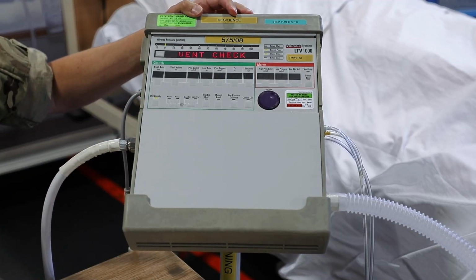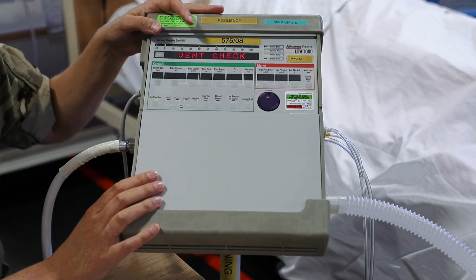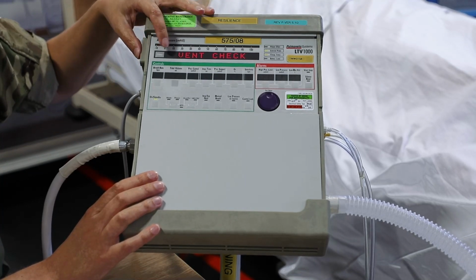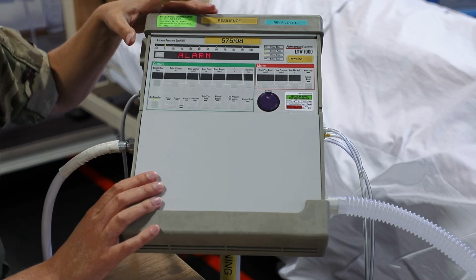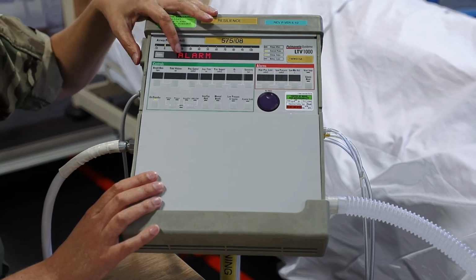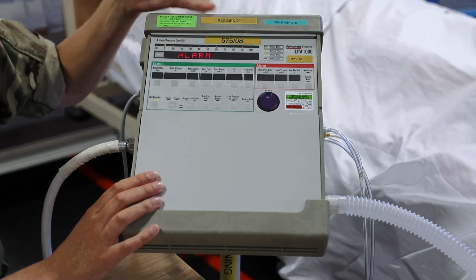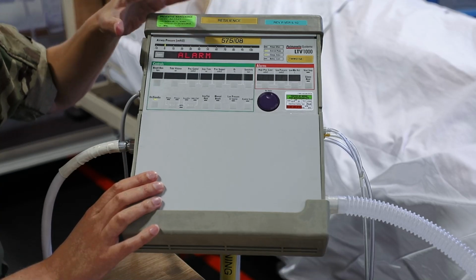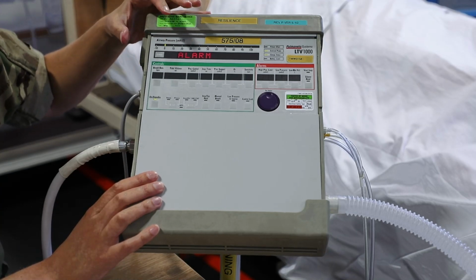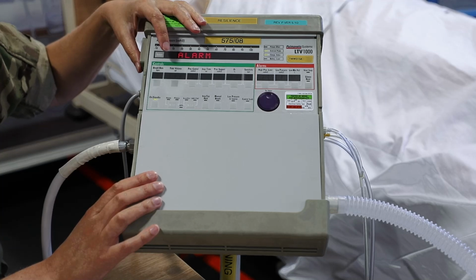So this first menu is the ventilator check menu, and to enter that menu we're just going to press select. The first option here is an alarm. Now what you've got to imagine is that these are menus within menus, and it can get quite confusing, but this is why it's really important that you follow that checklist all the way through.